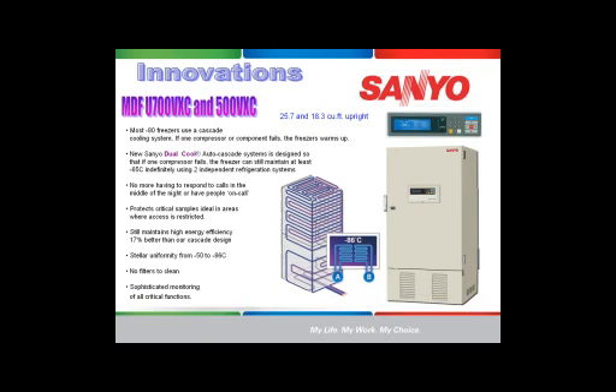So what it does is it allows you to maintain at least minus 65 degrees if one compressor fails for any reason. And for many of our customers, that's been a very big deal for them because they don't have to have people on call if a freezer starts to have problems. They don't have to be there in the middle of the night if there's any issues. It gives you much more peace of mind as far as protecting your critical samples, and we're still able to do that with better energy efficiency than our old cascade designs.